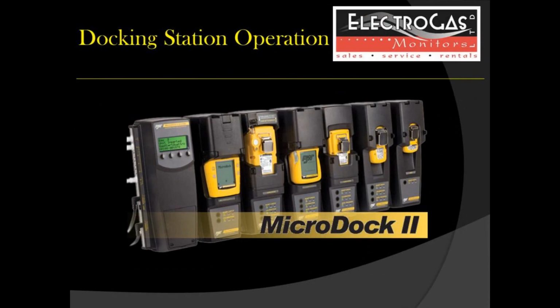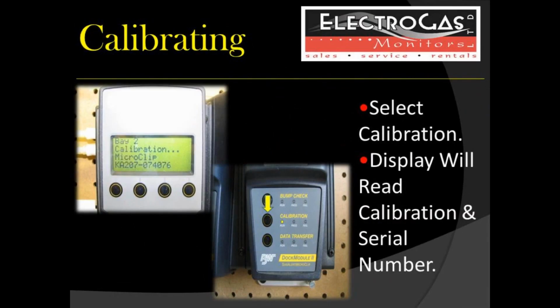We will now cover the calibration process using the BW MicroDock 2 system. As with bump testing, you must allow your monitor to warm up for 2 to 3 minutes, ensure your battery is adequately charged, and your charging or IR port is clean. You may now select the calibration option on the test bay. The display will again show calibration and the serial number of the monitor.